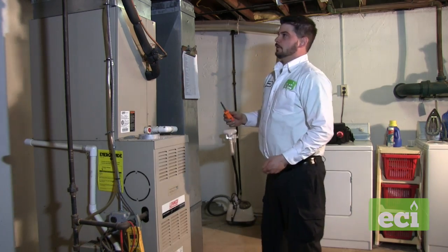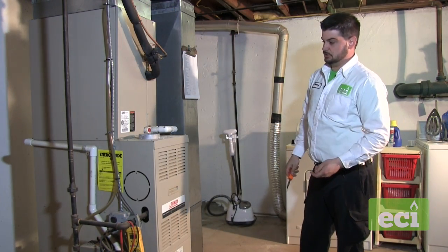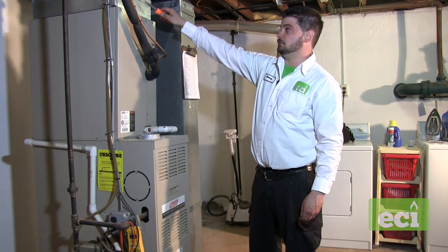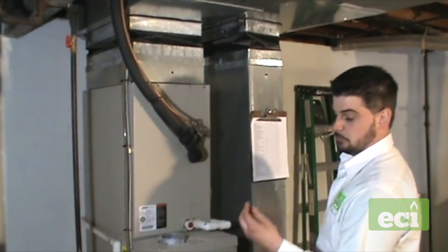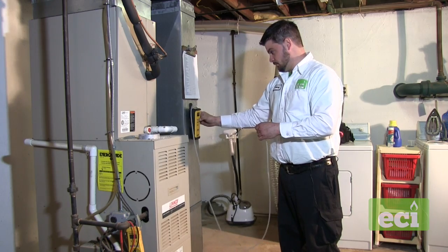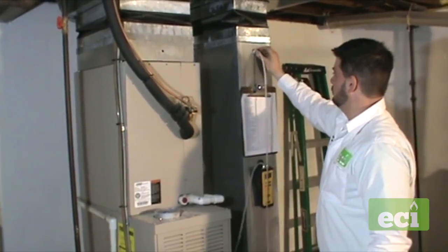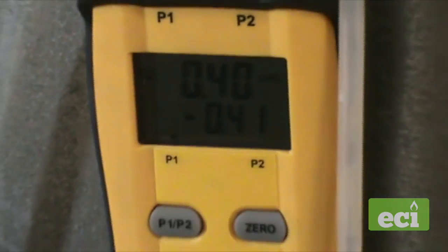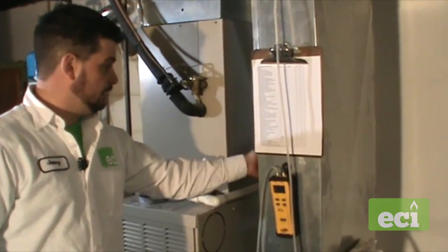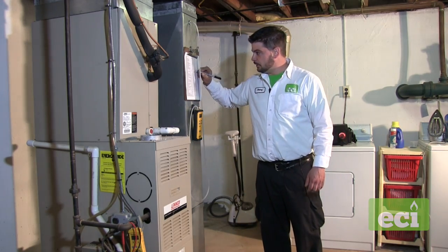We'll start it up and take some readings. We have holes in the return and supply already. There's also a hole on the back of the furnace to check static pressure on the return, before the coil, and above the coil. When you're done drilling a 3/8 hole, we put caps back in to make sure there are no leaks. Starting with the static reading on the return with the probe facing the airflow, I have a reading of negative 0.4, which is not that bad. High static pressure causes the ductwork to pop in and out, and customers hear a thumping noise when the unit starts and stops.